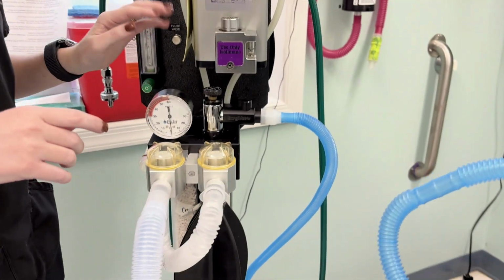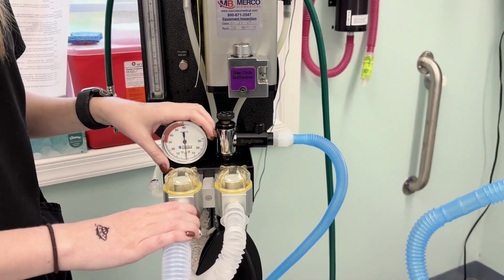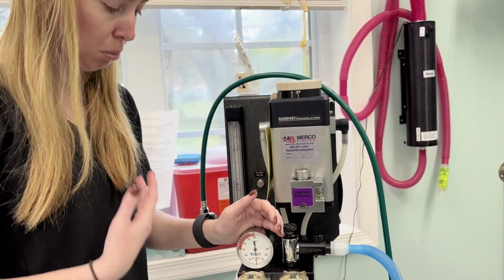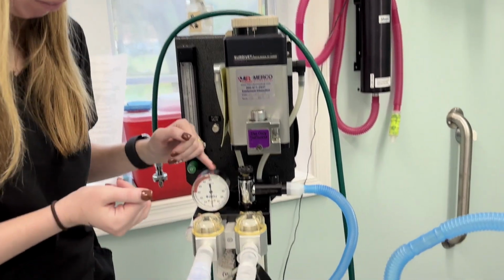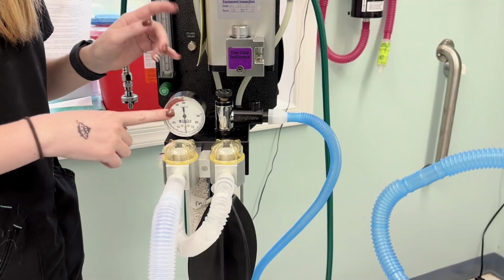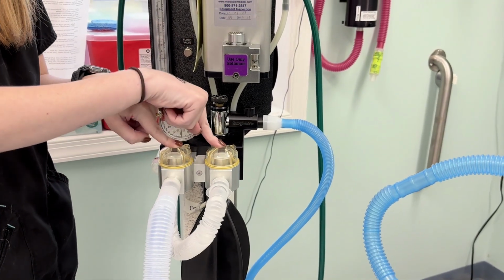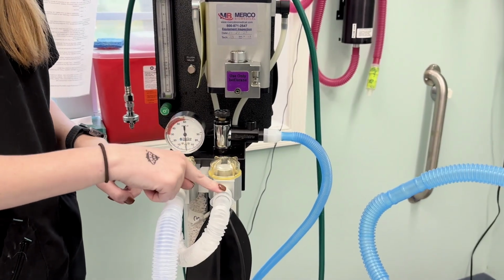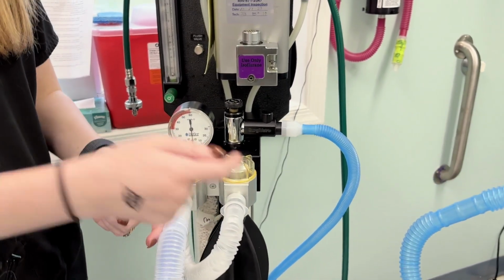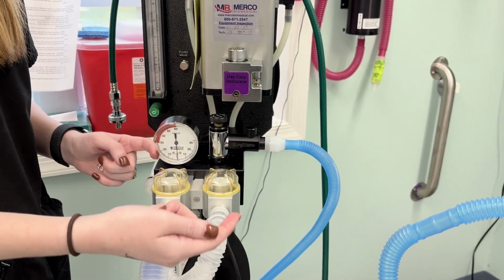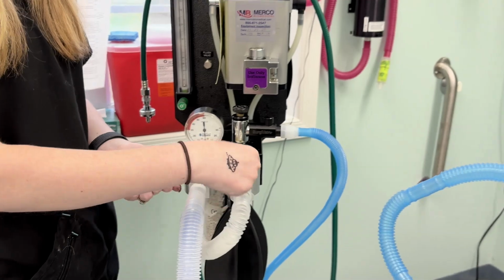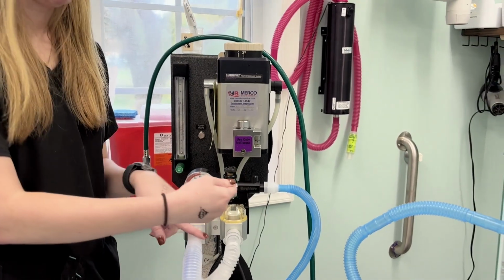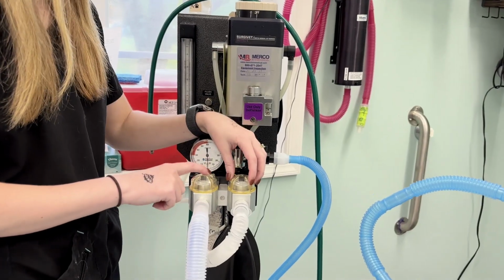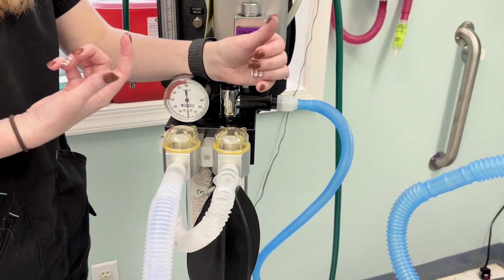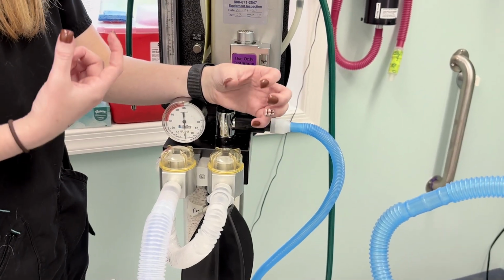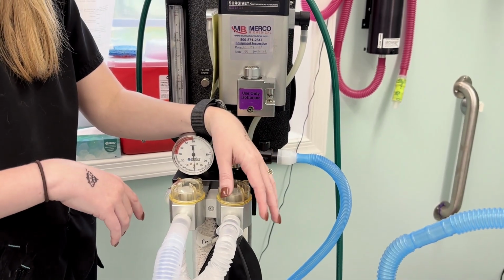Over here is our pressure gauge. This shows how much pressure is in the patient's lungs when you give a breath. You never want it to go above 20. These two are the unidirectional valves on the inhale and the exhale ports. This one's the inhale port, this one's the exhale port. They are one-way valves, so you have to make sure you're attaching things correctly to ensure that the patient is receiving and getting rid of their anesthetic gases. When the patient breathes, you'll see the white part go up when they exhale, and down when they inhale.